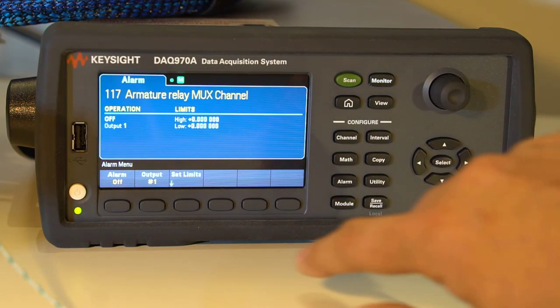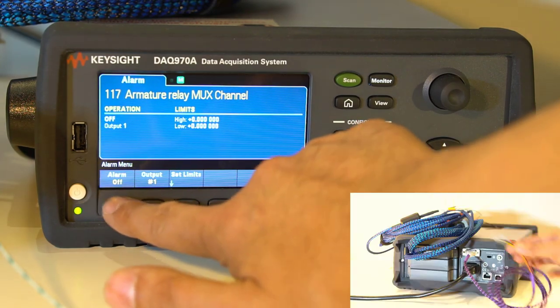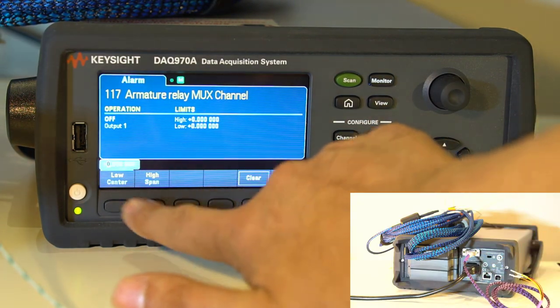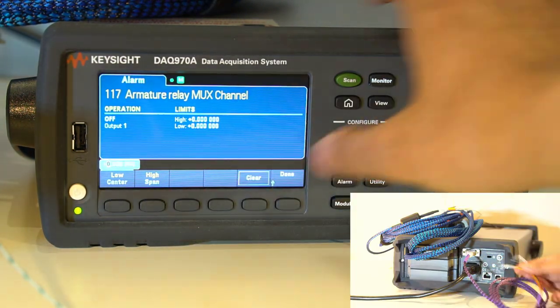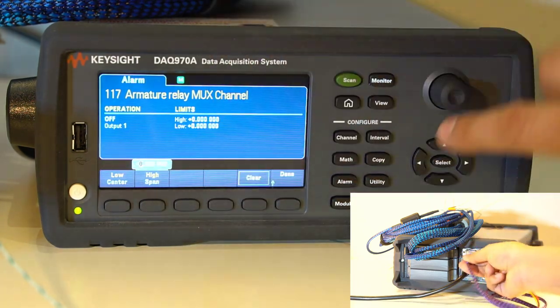A useful feature is the built-in alarm outputs. There are four of them at 3.3 volt logic levels, and they can latch or follow the assigned channels when a high or low threshold is exceeded.